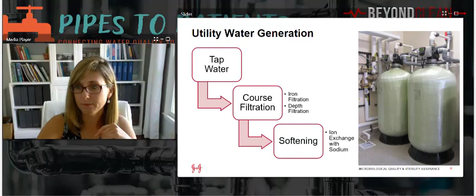Usually those steps will give you the right amount of quality, but there might be additional steps you need depending on your starting water quality level. So don't be surprised if even with utility water, you have additional steps that go beyond what's shown here. That will be identified as part of your water qualification system, and will be specified as a requirement in the upcoming ST108 standard.